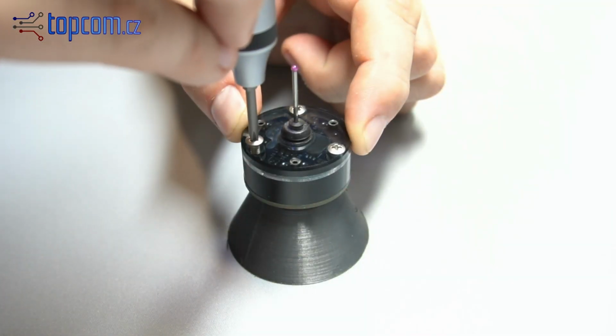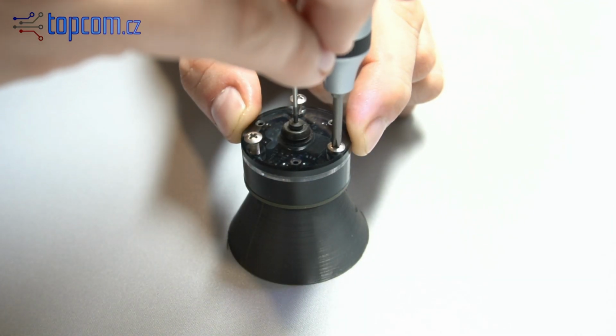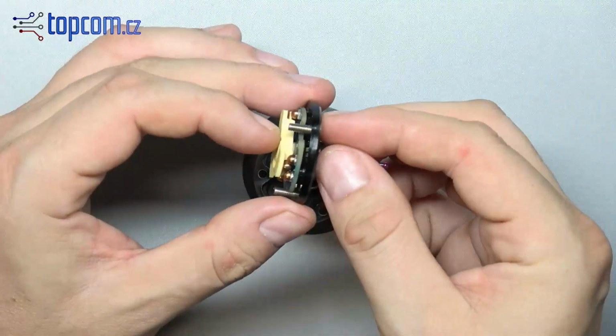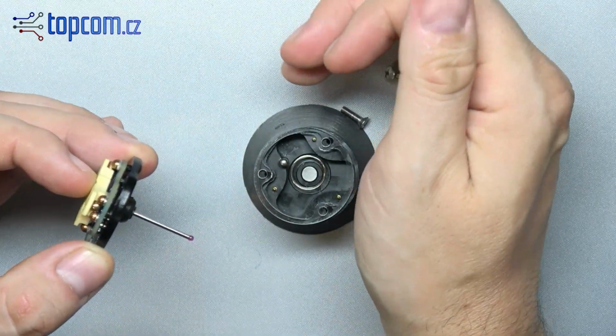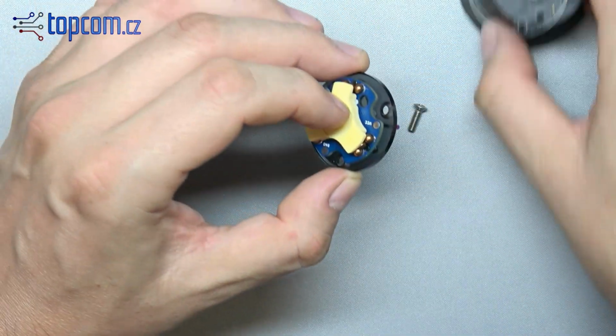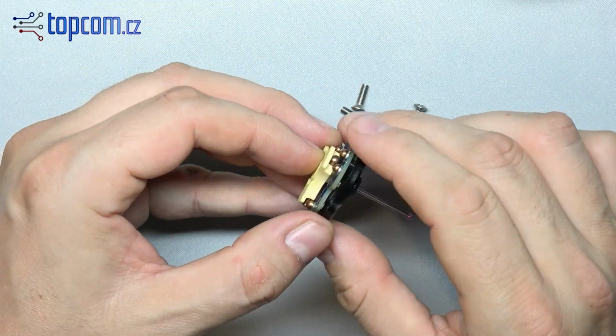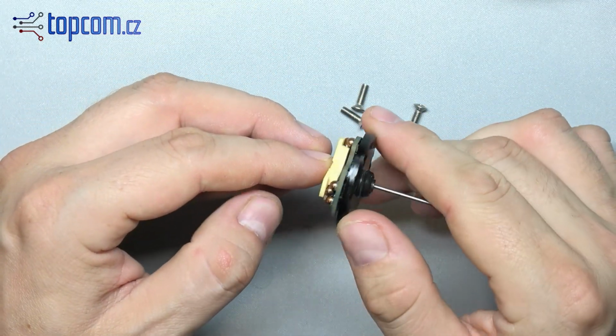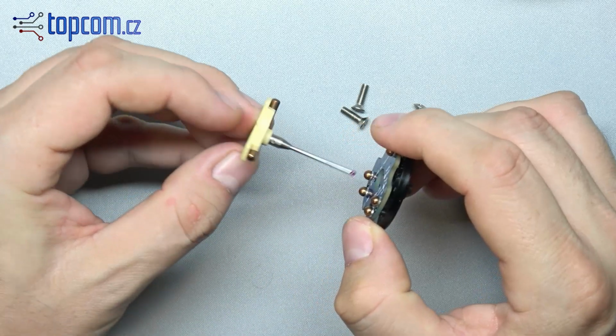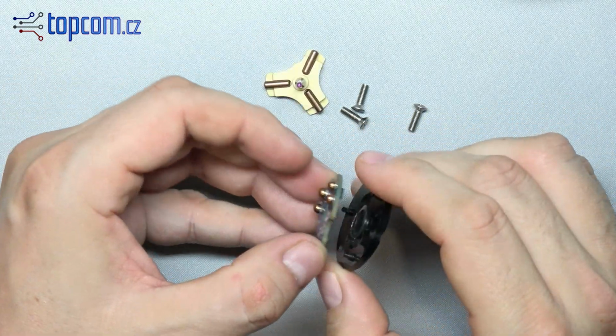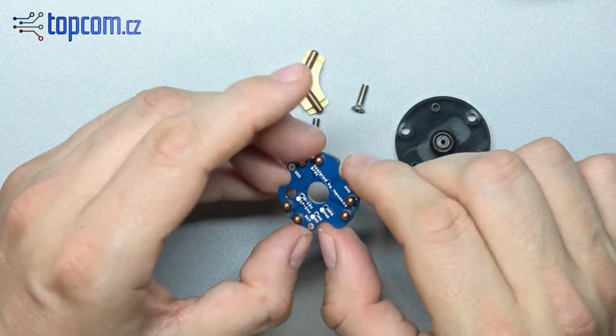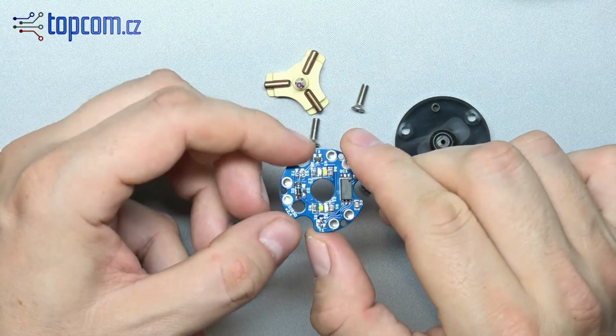First, unscrew the screws on the bottom side of the probe. Open the probe and check that everything inside is in proper condition. You may also perform contact maintenance if needed. The contacts can be cleaned using a soft cloth or compressed air. It's recommended to apply a drop of silicone oil to the contact surfaces for optimal performance.